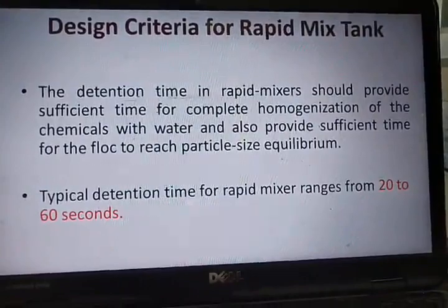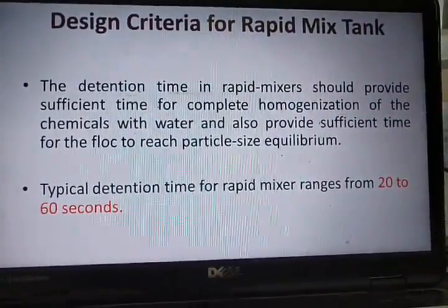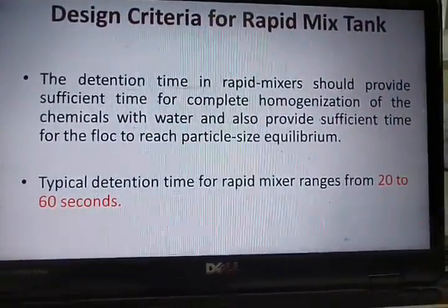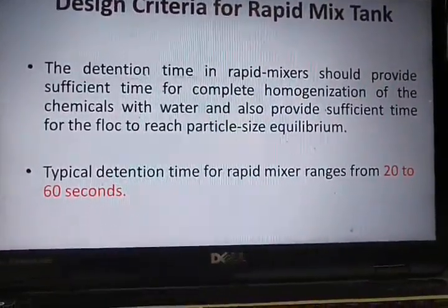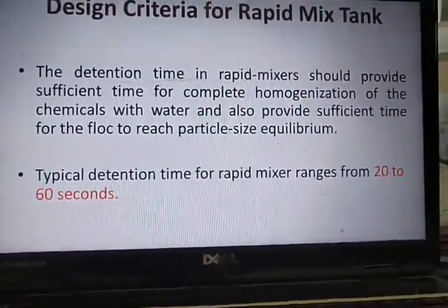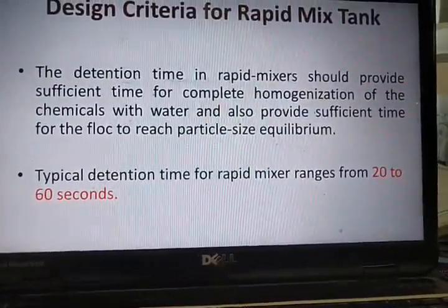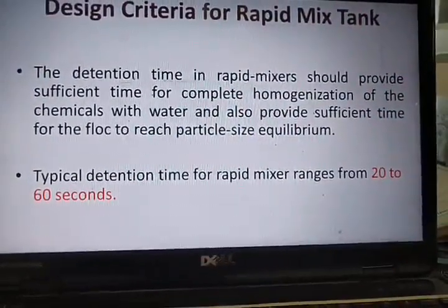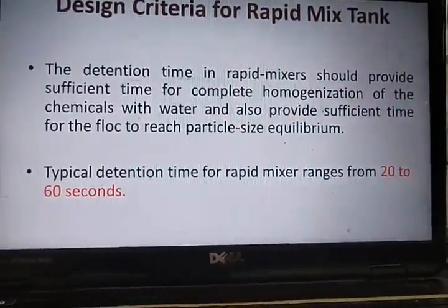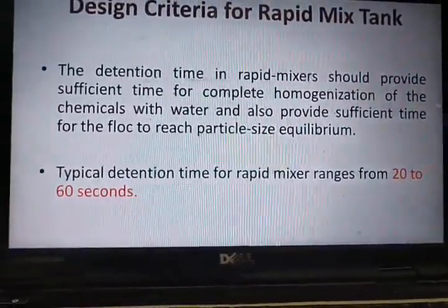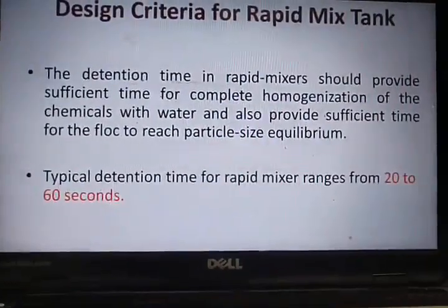Now the design criteria for a rapid mix tank. It is a very small chamber, sized based on the capacity of the water treatment plant, but the important design parameter here is the detention time. Typically the detention time ranges from 20 to 60 seconds, or up to 1 minute.